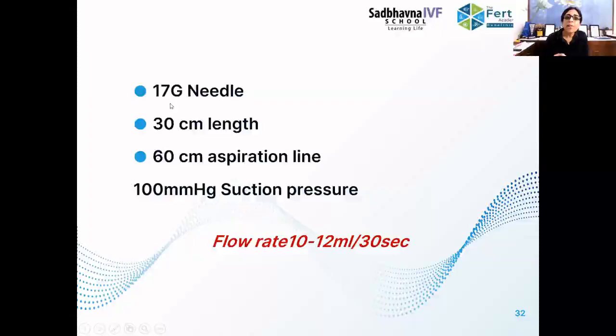So this is the way we validate our suction pump after about 2 months. We check whether, when we keep it at 100, the flow rate comes at 10 to 12, which means the pressure is 100 mm of mercury. These are the variables you use, and you get a flow rate of 10 to 12 ml per 30 seconds. Suppose you use a needle which is smaller in diameter, then of course you will have to increase the pressure to have the same flow rate.